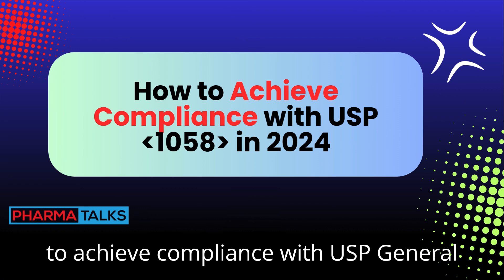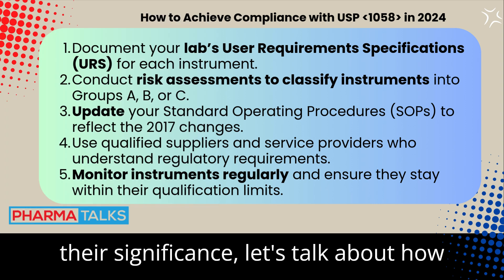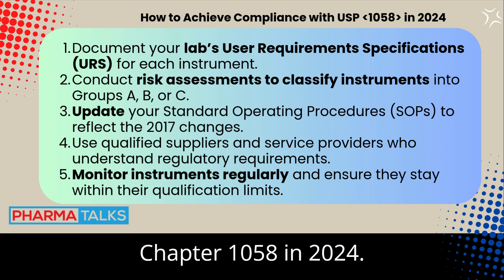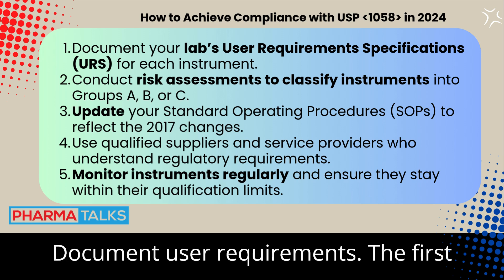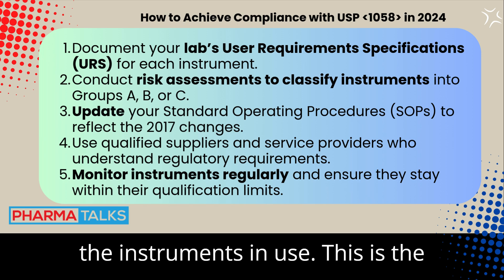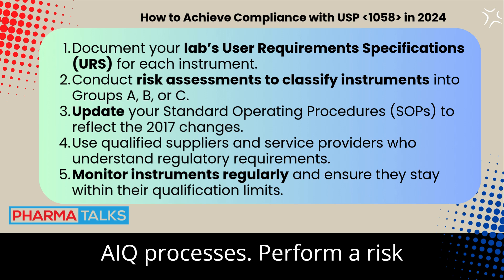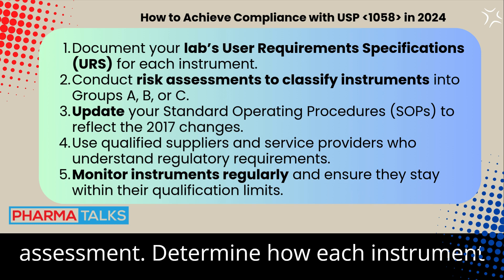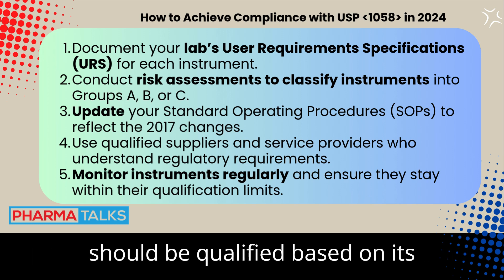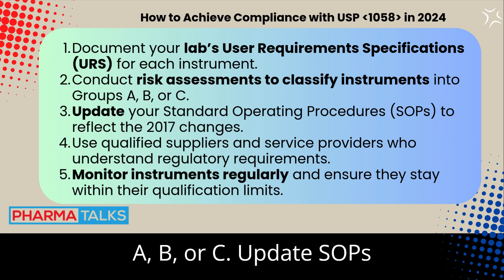Here's how to stay compliant with USP General Chapter 1058 in 2024. First, document user requirements — clearly document your lab's needs and the technical requirements of the instruments in use, as this is the foundation for your risk assessment and AIQ processes. Second, perform a risk assessment to determine how each instrument should be qualified based on its complexity and intended use, and use this to classify instruments into groups A, B, or C.